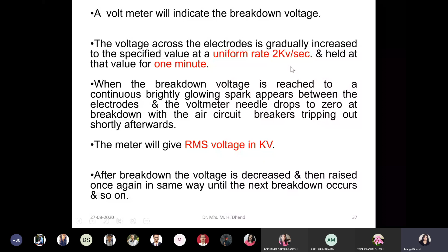Step up transformer. Then the rate of change of voltage is 2 kilovolt per second, because if you vary it with another rate, the breakdown voltage will change. The meter gives the RMS value, which we have already discussed. And for oil testing, 6 readings are required. And if you test as per the IS, then your oil should withstand 30 kilovolt. Generally for oil you can remember 40 kilovolt and for air you remember 30 kilovolt. So oil 40 kilovolt and air 30 kilovolt.